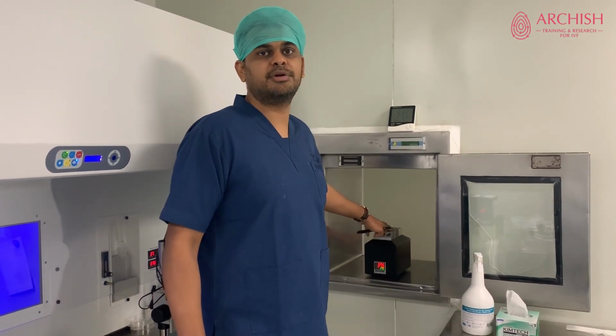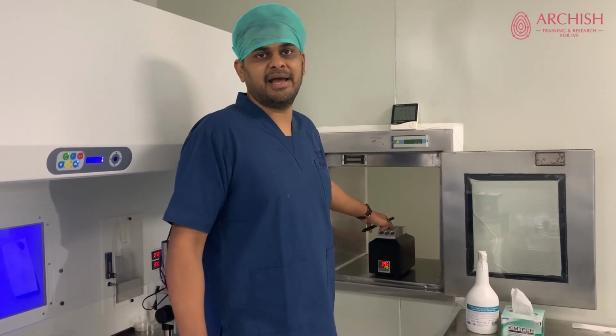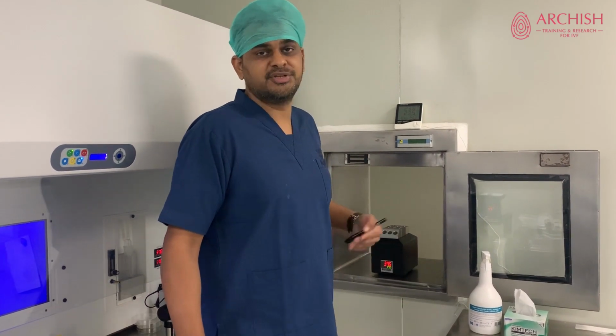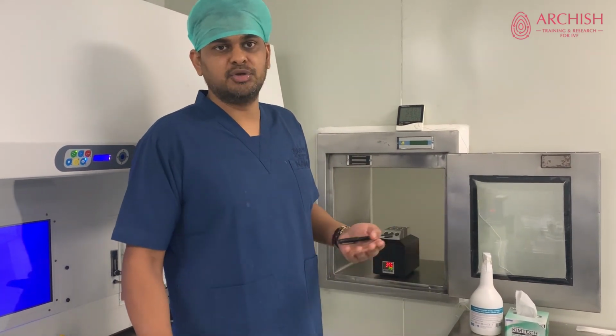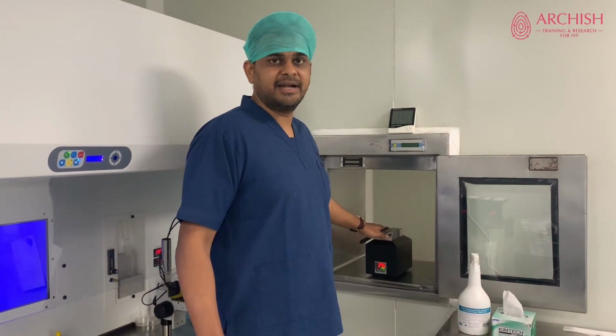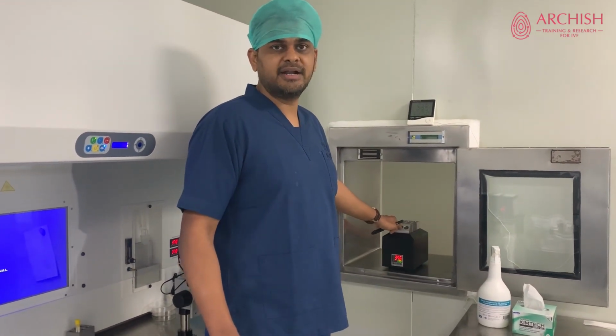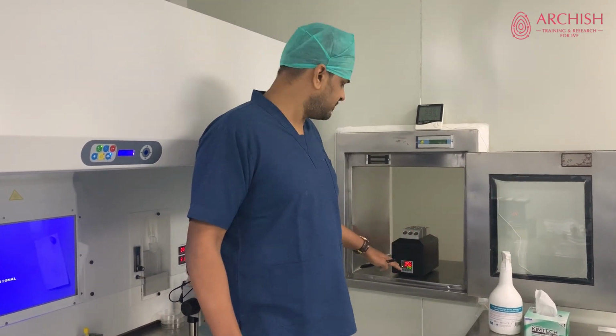If not, the blood is going to get clotted and you're not going to have the eggs that you were desiring, or which you might have thought you have stimulated. It also gives you an important understanding of what is the temperature displayed on the machine versus what you get on the temperature probe. That tells you which is at fault - is the temperature probe at fault or is it the instrument? That's why it's important to have a daily check of these aspects, because it's important that all of them are at 37 degrees plus or minus 0.5 degrees.